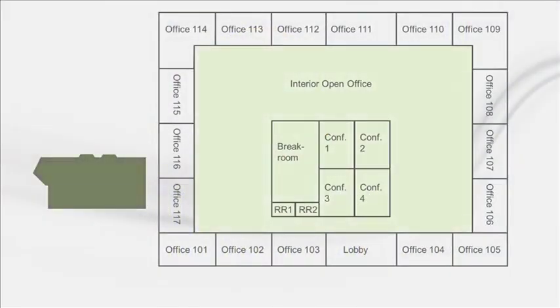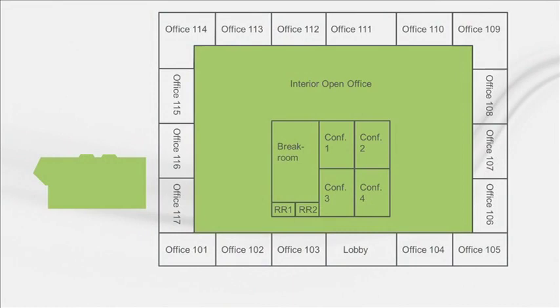In the summer, they will all require cooling, so the sizing will be dictated by the sum of all the loads. In the winter, the indoor cooling load and the fresh air heating load can be used to offset each other, and energy savings can be realized. Zoning is difficult, but modeling tools might make it easier. They can certainly help with determining annual design cooling and heating loads. So let's talk about building simulations and VRF for a bit.